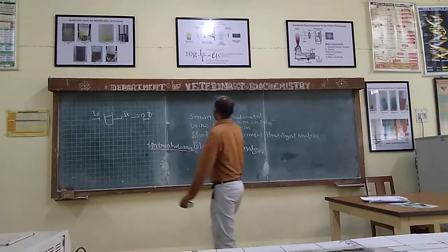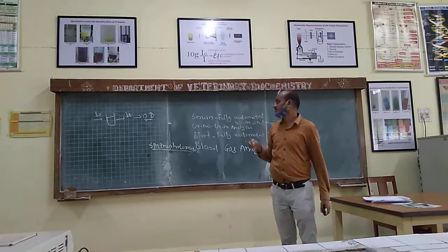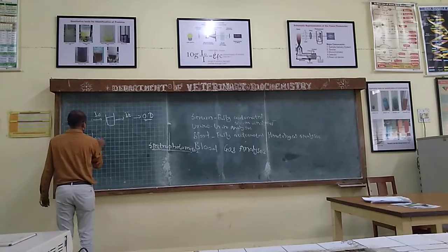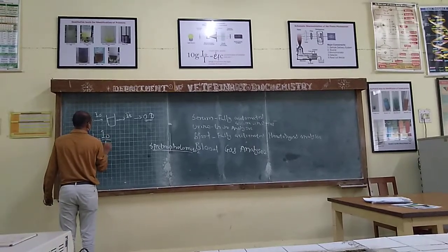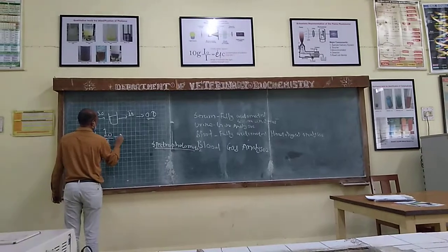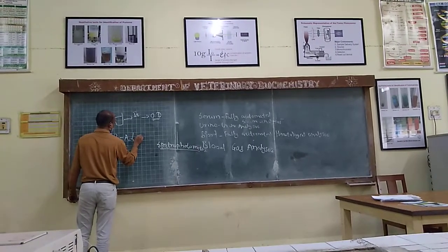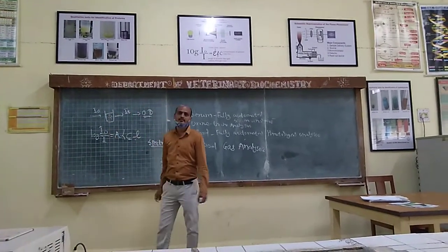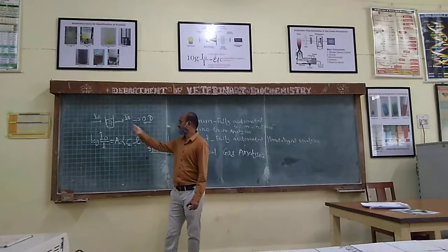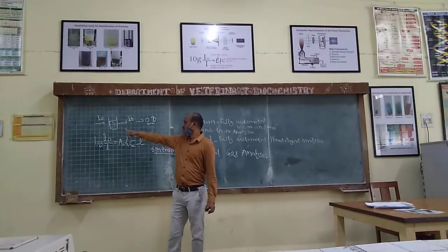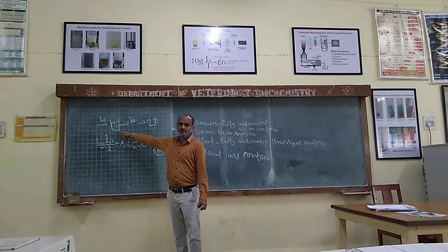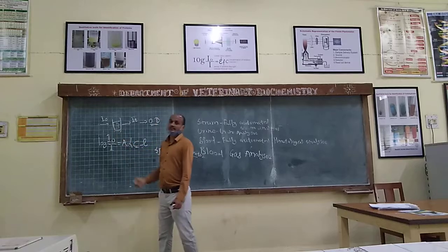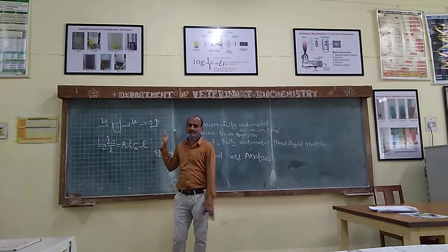This optical density reading, roughly we can say it is absorption, not exactly, but it can be expressed as the log of incident light divided by transmitted light, that is absorbance, which is directly proportional to C lambda. That means the concentration of this glucose. If the concentration of the glucose is more, the color will be more intense. So this is the principle for this colorimeter. It is also proportional to the path length, but for this purpose we are treating it as a constant.